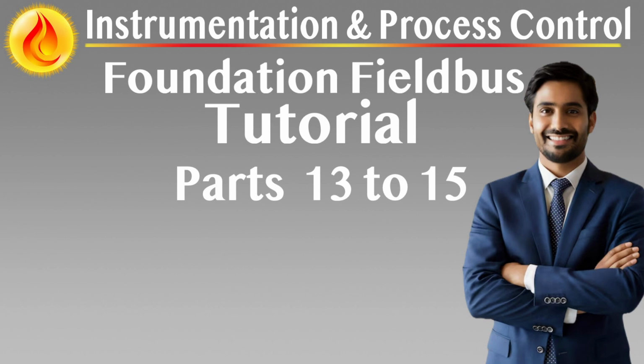Each segment must include exactly 2 terminators, one at the host or power supply end and one at the farthest junction box. These must be 100 ohm resistors in series with 1 μF capacitors installed in compliance with the physical layer requirements. Incorrect termination, too few or too many, can result in reflections, signal distortion, or complete segment failure. Technicians must verify and document terminator locations and resistance values before proceeding to energization.